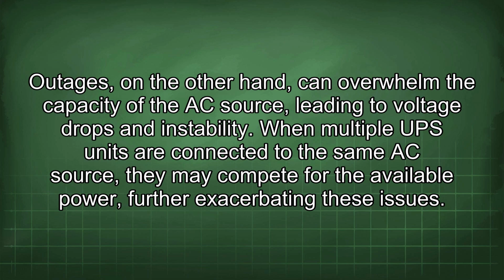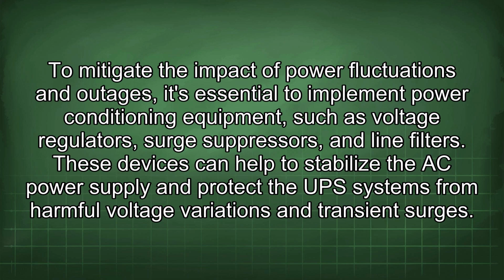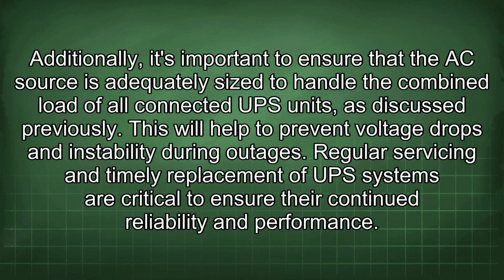To mitigate the impact of power fluctuations and outages, it's essential to implement power conditioning equipment, such as voltage regulators, surge suppressors, and line filters. These devices can help to stabilize the AC power supply and protect the UPS systems from harmful voltage variations and transient surges. Additionally, it's important to ensure that the AC source is adequately sized to handle the combined load of all connected UPS units, as discussed previously. This will help to prevent voltage drops and instability during outages.